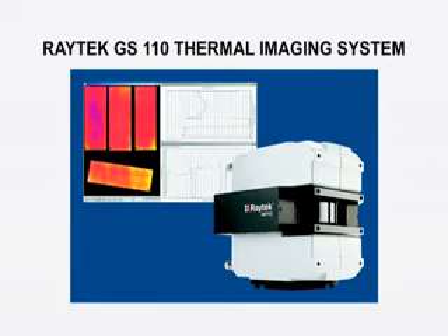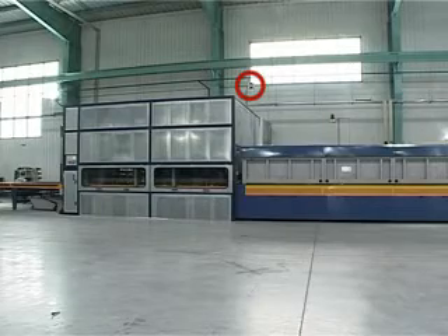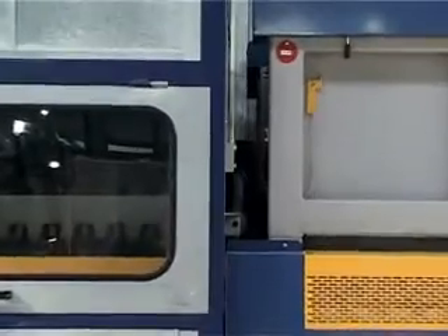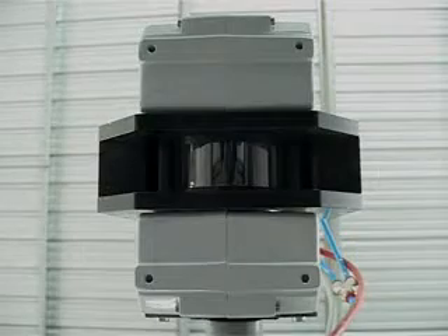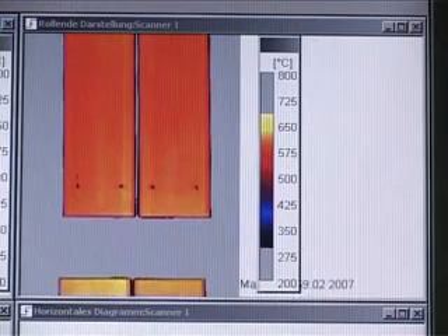The Raytek GS 110 thermal imaging system is specifically designed to monitor the temperature distribution of low-E glass. The heart of the system is an advanced infrared line scanner, mounted above the small gap between the heating and the quenching section. Just like a camera, the scanner views the heated glass sheets from above and scans their surface as they pass its field of view. Another sensor measures the temperature on the uncoated bottom side of the glass.